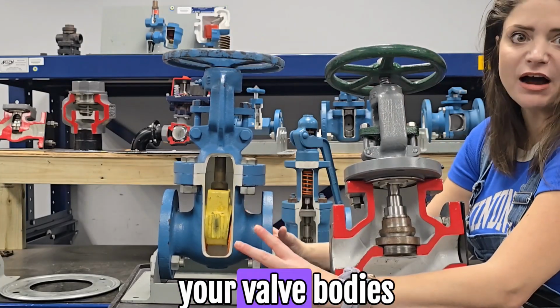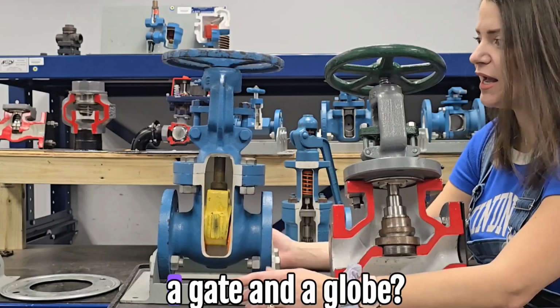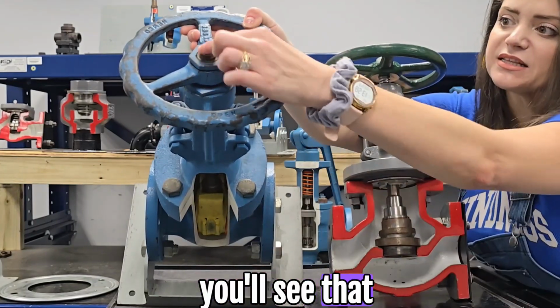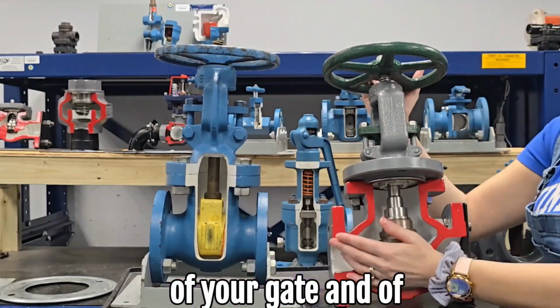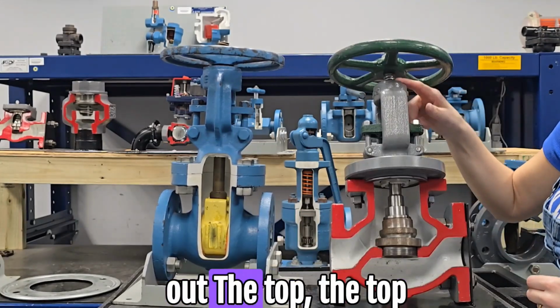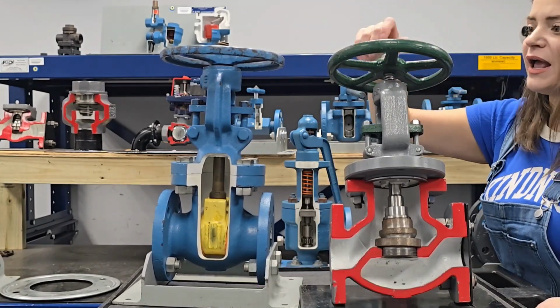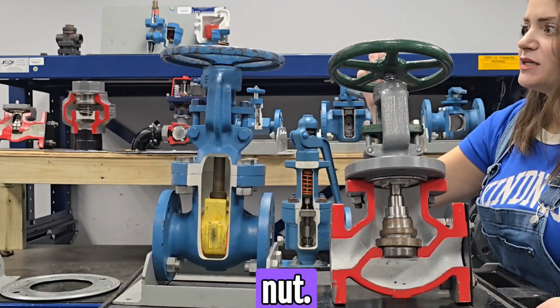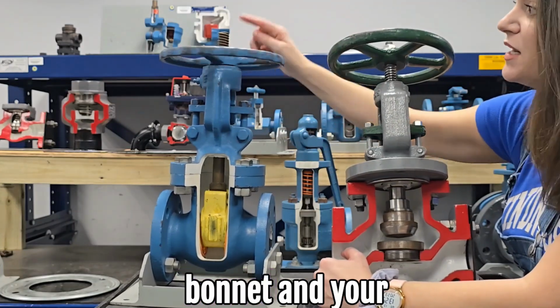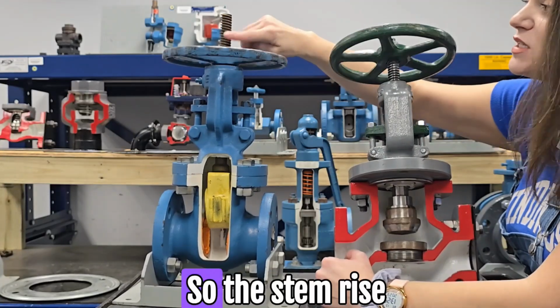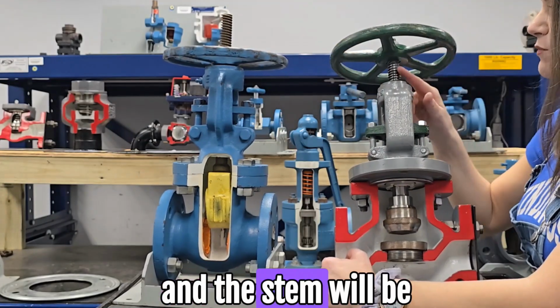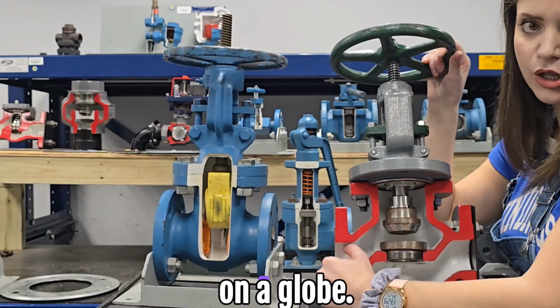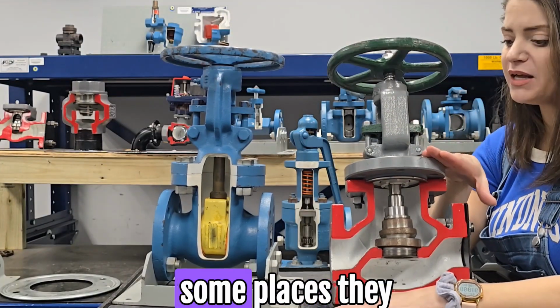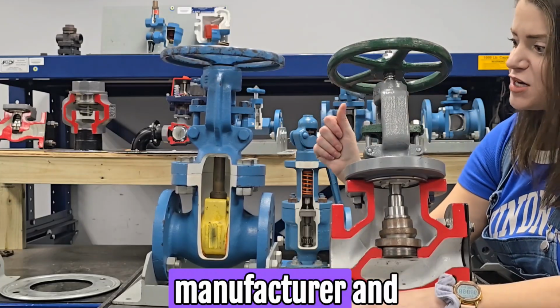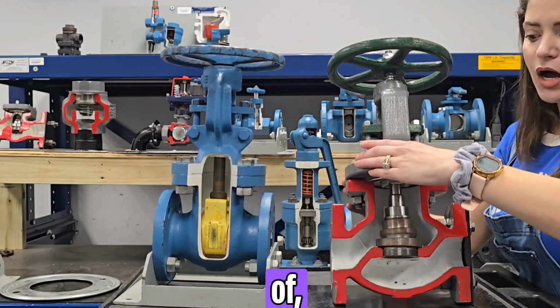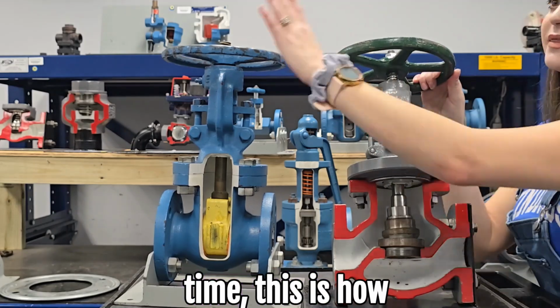Your piping and your valve bodies are usually insulated. So how do you tell the difference between a gate and a globe? Well, you look up top. You'll see that there's a little bit of stem hanging off the top of your gate, and on your globe, you have a little bit of threads hanging off the top. The top of your globe valve hand wheel is going to have a screw and nut. Your hand wheel is attached to your bonnet and your stem rises above the hand wheel. So the stem will rise above the gate valve's hand wheel, and the stem will be underneath and between the bonnet and the hand wheel on a globe. And this is like 90% of valves. Some places have a different design, where it's a certain manufacturer and it's actually the shape of the bonnet. But majority of the time, this is how you're going to be able to tell.